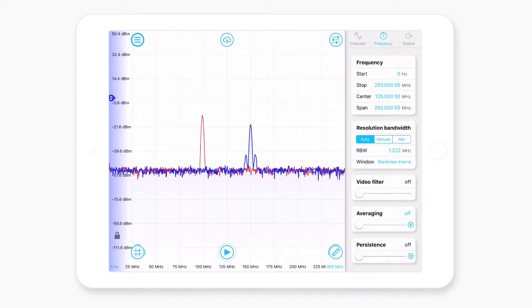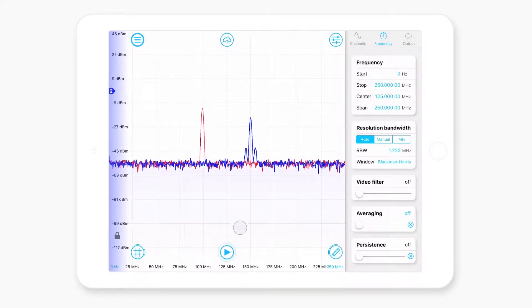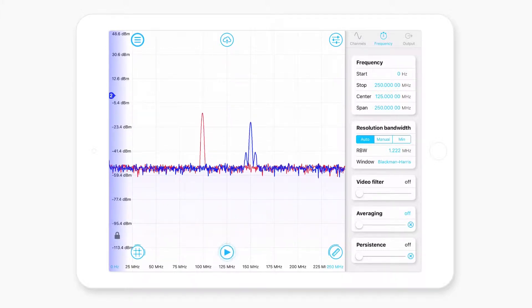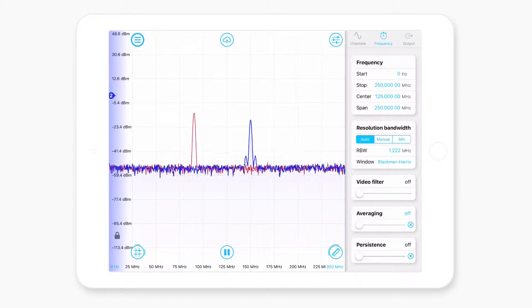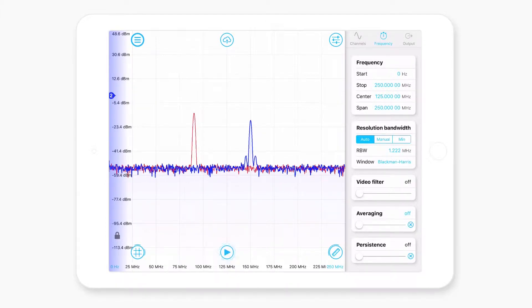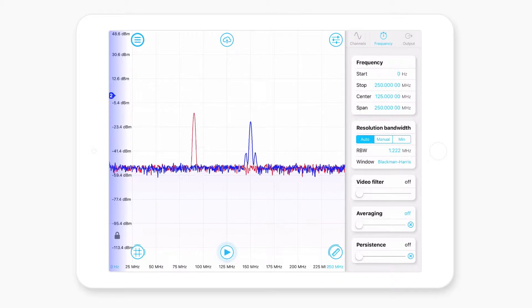So to resume a measurement, you'll notice that there's a little play button down the bottom here that is drawing our attention towards it. It's because in order to resume the measurement, we have to click it. And so we might as well explain this. So if you wanted to pause a trace for any reason to take a measurement, then you just hit the pause button and then resume.